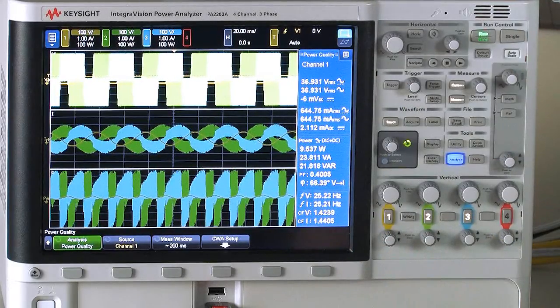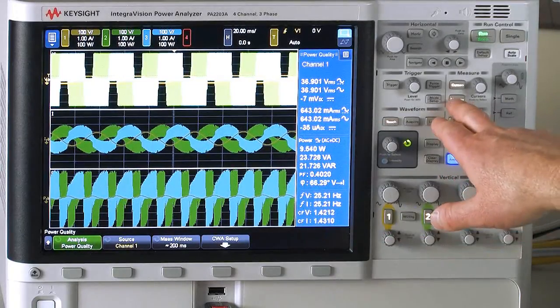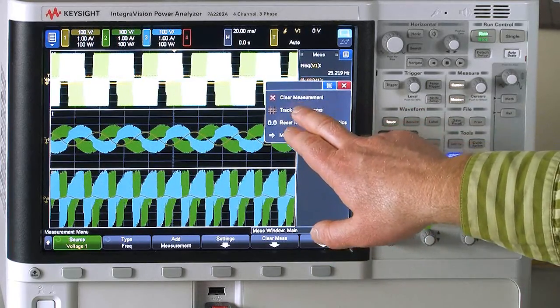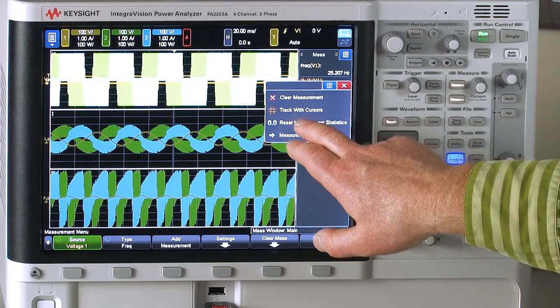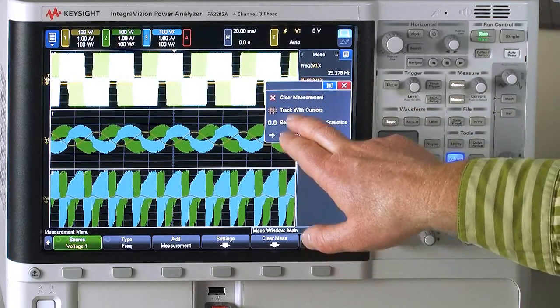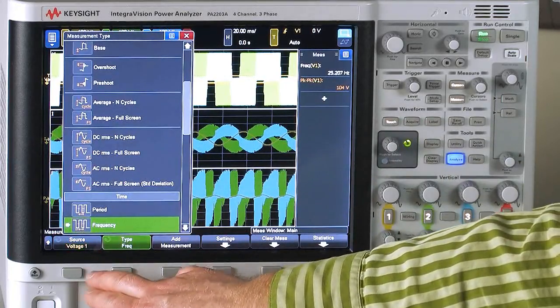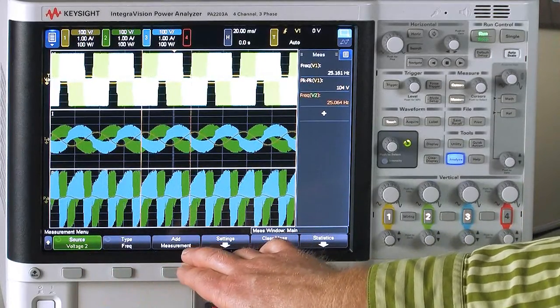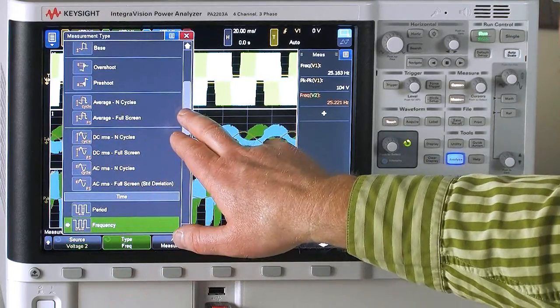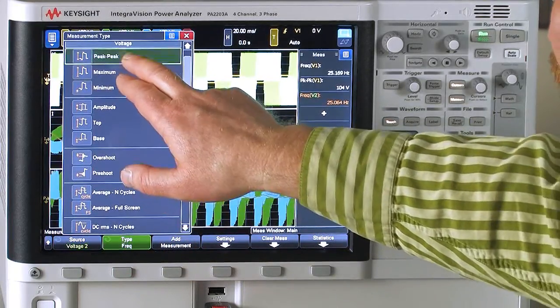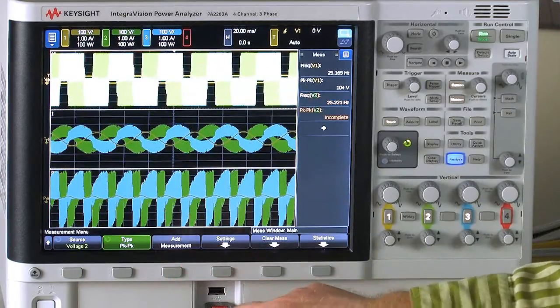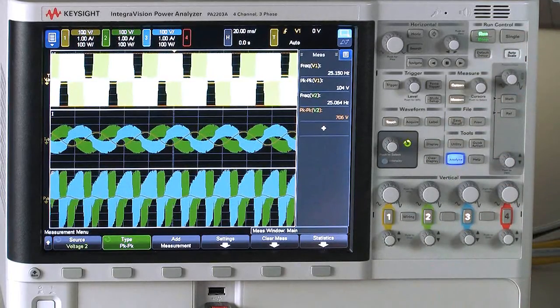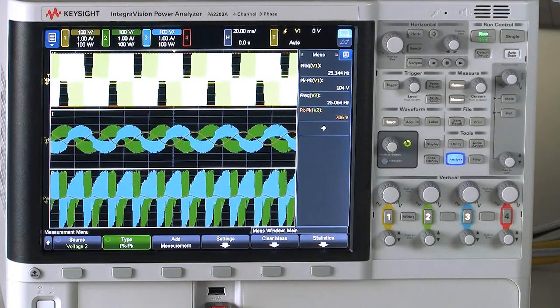And I've got a sinusoid that's 36 volts, but the peak to peak on this thing was, well, on channel one, the peak to peak was 100 volts. But if I look at the peak to peak on the actual PWM signal, I can look at channel two. And that's measuring about 700 volts. So that's the rails of the actual VFD, the DC rails internal to the VFD.